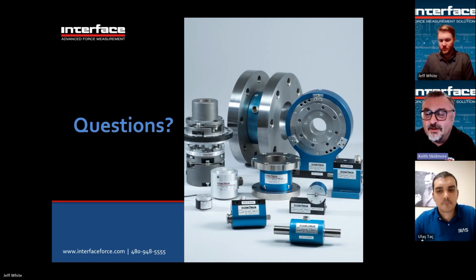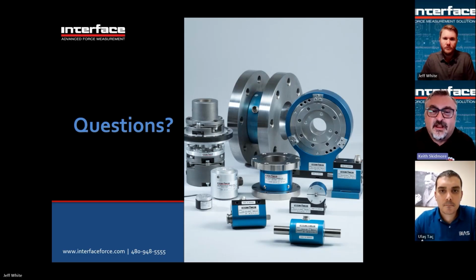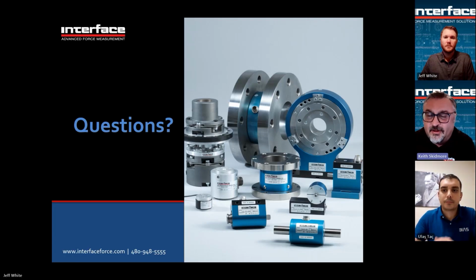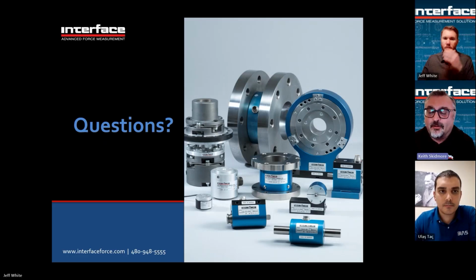There are also torque sensors that have software included, that have digital outputs. Those software packages typically display graphs and log data, and they have adjustments that can be made for filtering and bandwidth and whatnot. We also have instrumentation that runs relatively high bandwidth. So if somebody wants to measure, say, high dynamic features of a torque signal, we do have boxes that would sit between the torque sensor and a PC that can take the signal, maybe sampling up to 40,000 samples per second, and that can be turned down or decimated, but you have a high sample rate internally, so you can capture spikes or features.